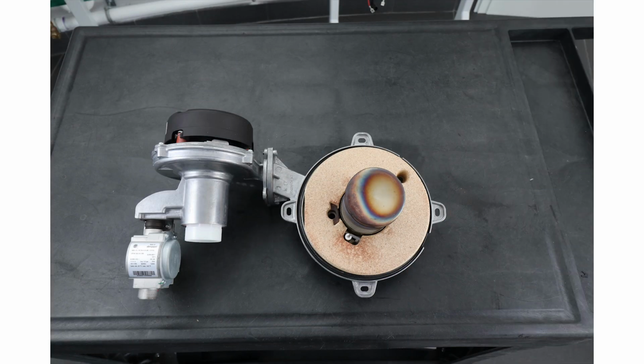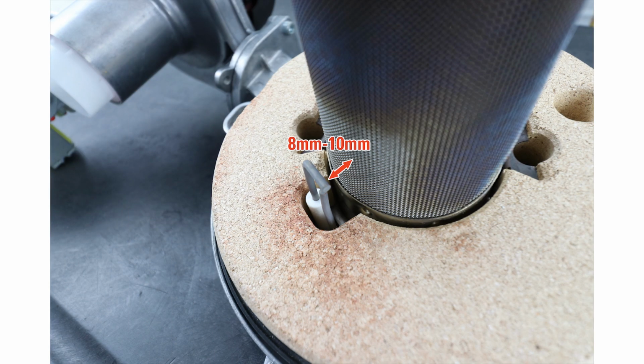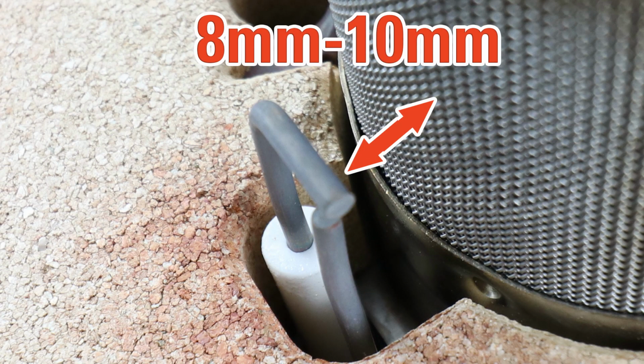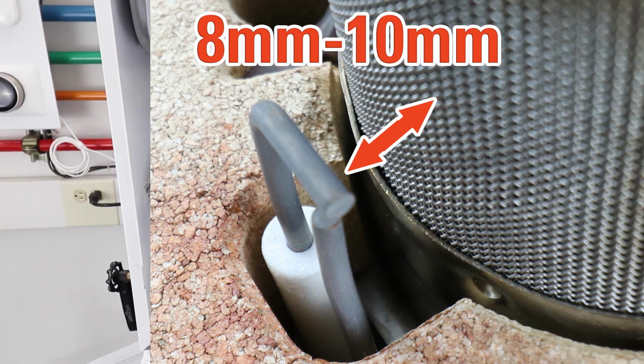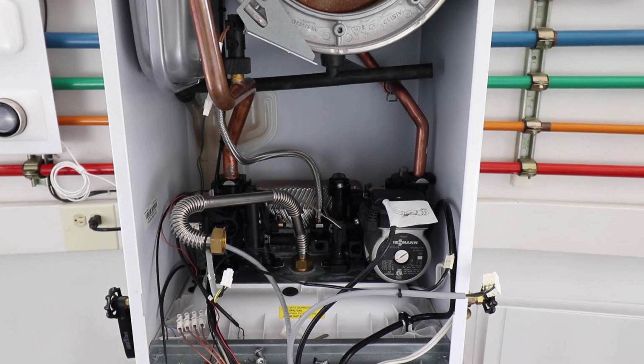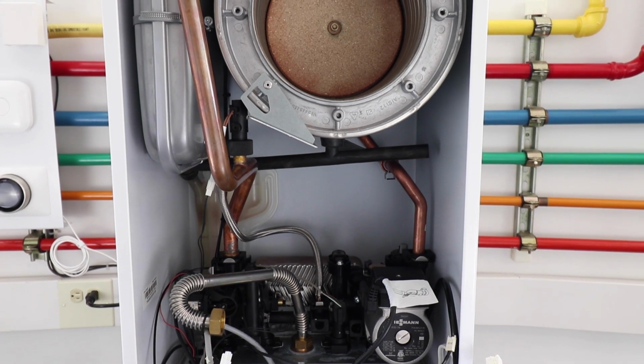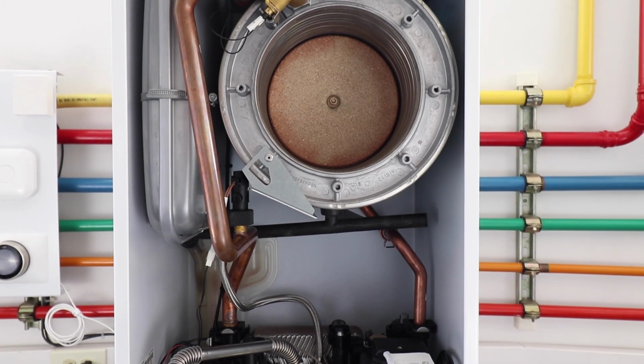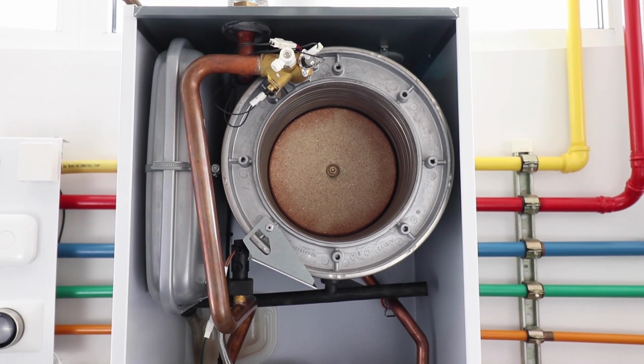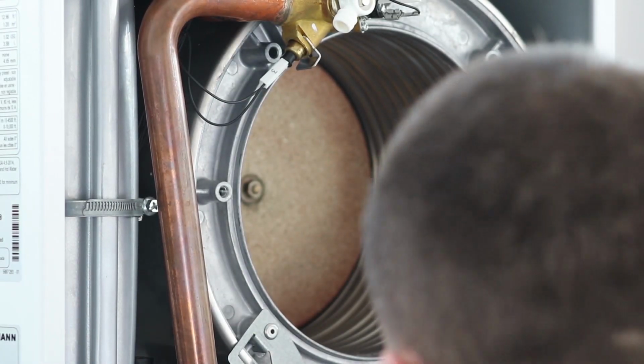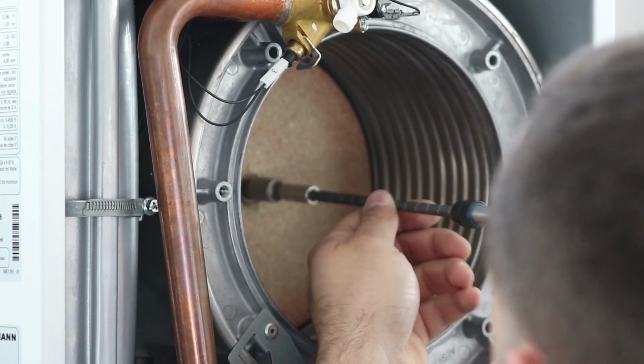Next, lay the burner assembly on a flat level surface. Be sure to inspect the electrode gap. Remove the rear refractory before cleaning the heat exchanger.